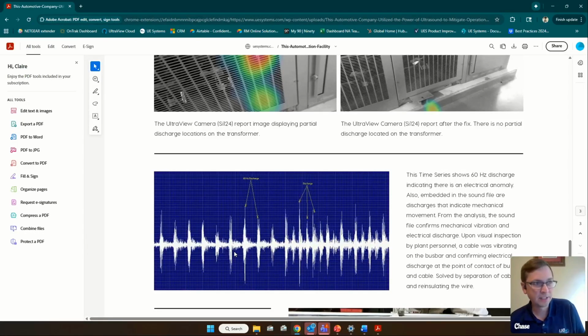As you look at the sound file in this area, the harmonic markers kind of double up. After I put a couple other harmonic markers up on the screen, it confirmed that it was basically mechanical vibration. Normally you get that in MCC rooms with a nameplate or a bolt on the cabinet that's not fastened on properly.